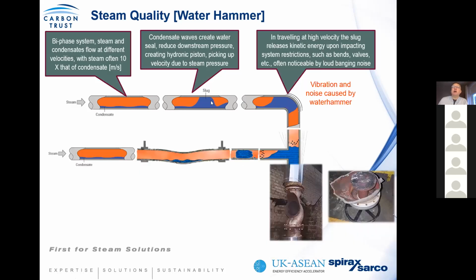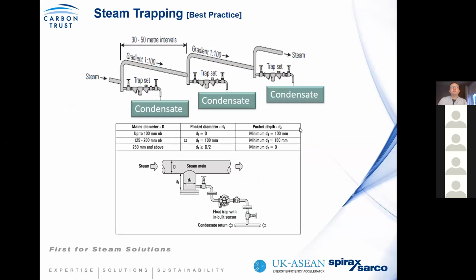However, if you then look at ineffective condensate management, condensate drainage, the consequences are, we have come across case examples where valves have been destroyed purely because the continuous water hammer damage has damaged the structural integrity of the valve. And again, you see cases where valves break and shear, releasing steam, which can be a health and safety hazard, irrespective of the energy. And again, multiple case examples where valves and system equipment have been destroyed because of this water hammer. However, this is addressable because it's about steam system fundamentals. So when we start looking at our steam distribution system, there are best practice guidelines on condensate removal to remove this water hammer issue.